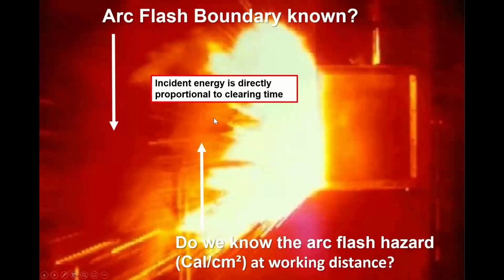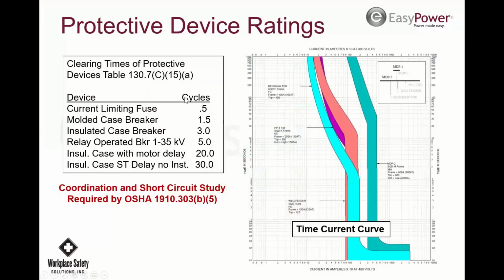So we talked about the clearing time. So here's the table in NFPA that gives you some idea of clearing time. So current limiting fuses, a half of a cycle. Molded case breaker 1.5 goes all the way up to 30 in the table. This is the section in OSHA that says that you need to do a coordination and short circuit study in so many words. But a lot of people don't realize that it's even part of OSHA.